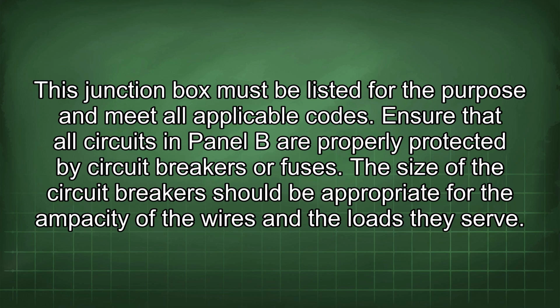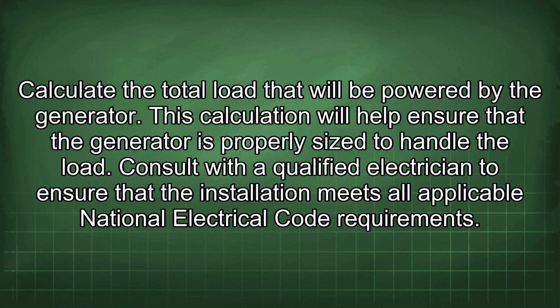Ensure that all circuits in panel B are properly protected by circuit breakers or fuses. The size of the circuit breakers should be appropriate for the ampacity of the wires and the loads they serve. Calculate the total load that will be powered by the generator. This calculation will help ensure that the generator is properly sized to handle the load.